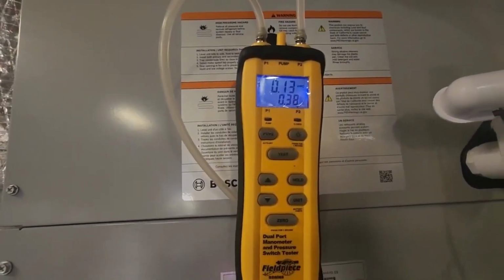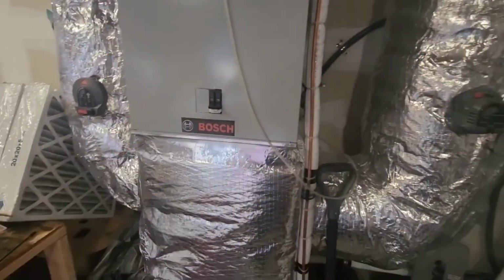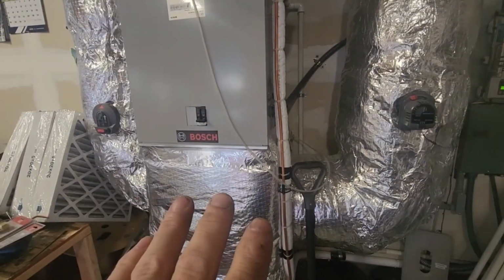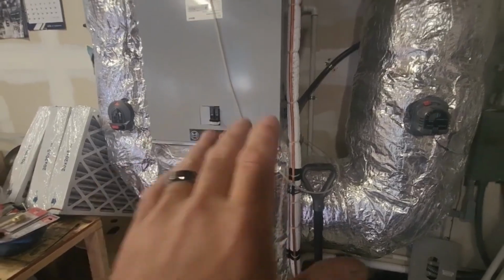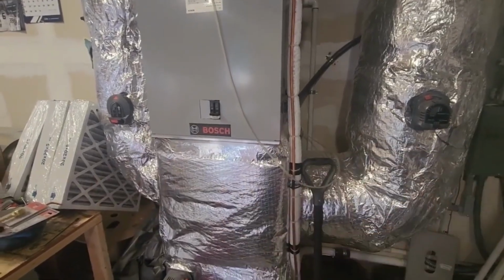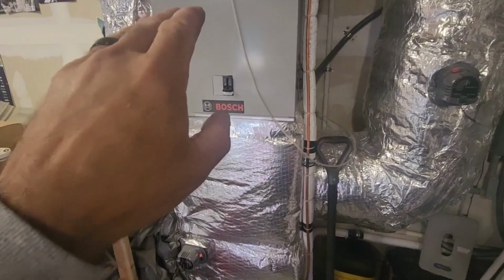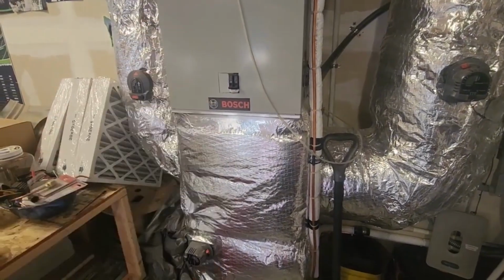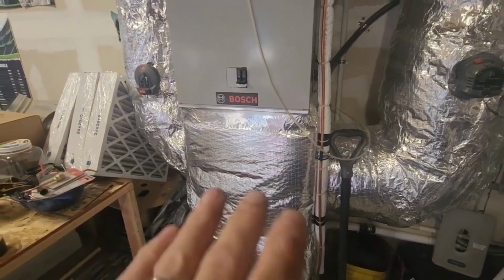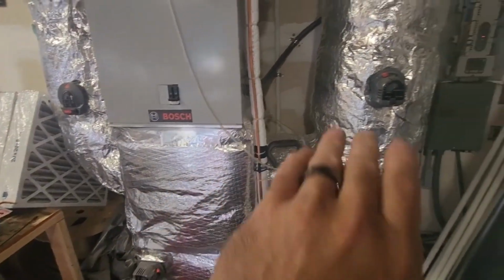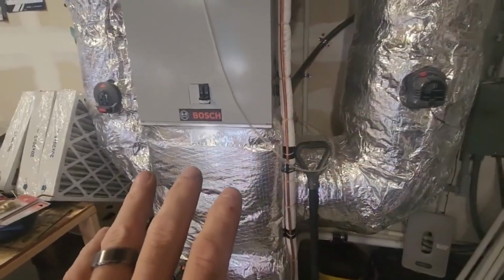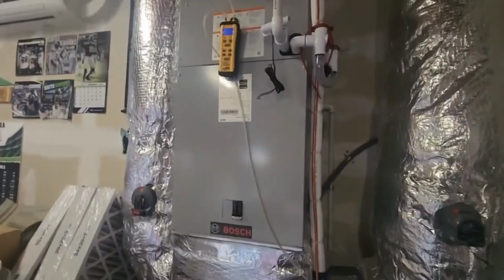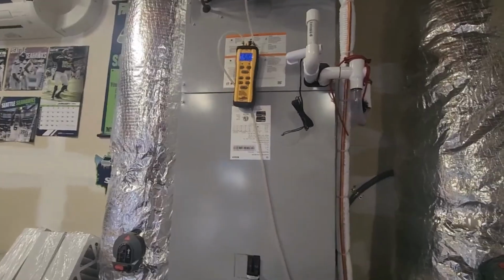It's even a little bit less. And the reason for that is it will not go into second stage equipment or second stage cooling on the condenser, and it'll only be on its first stage of the fan. So it's just pushing enough air through there, and it will never ramp that fan up, no matter what the thermostat says.